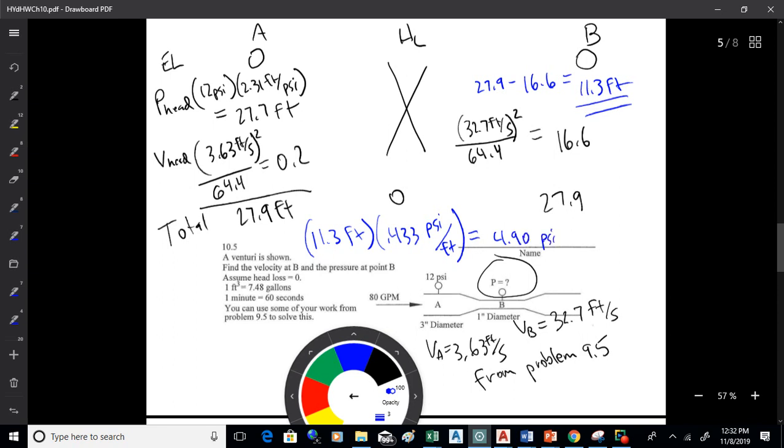So just by pushing the water through that venturi, as it's called, you're dropping the pressure by about 7 psi. And the reason is you're making the water go a lot faster, and when it goes faster, the energy required for the velocity head goes up, and it has to come from somewhere, and where it's coming from is pressure.